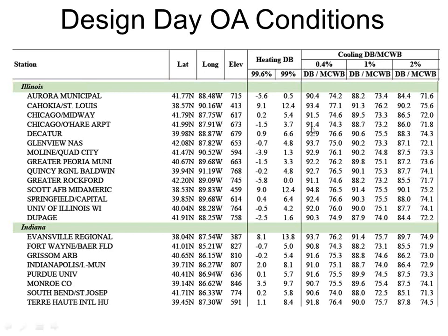I get that it could happen and every once in a while it does, but from a design standpoint, we should be designing for 91 or less outdoor temperature. On the heating side, by the way, as a point of reference for O'Hare, it's minus 1.5. And as you get closer to the city, it gets a little more mild.